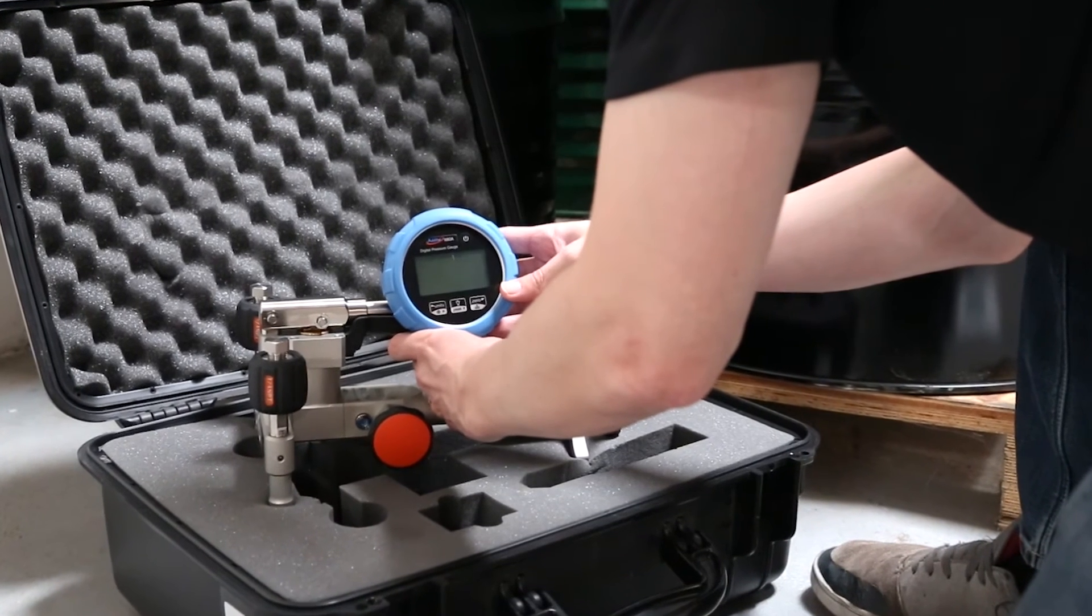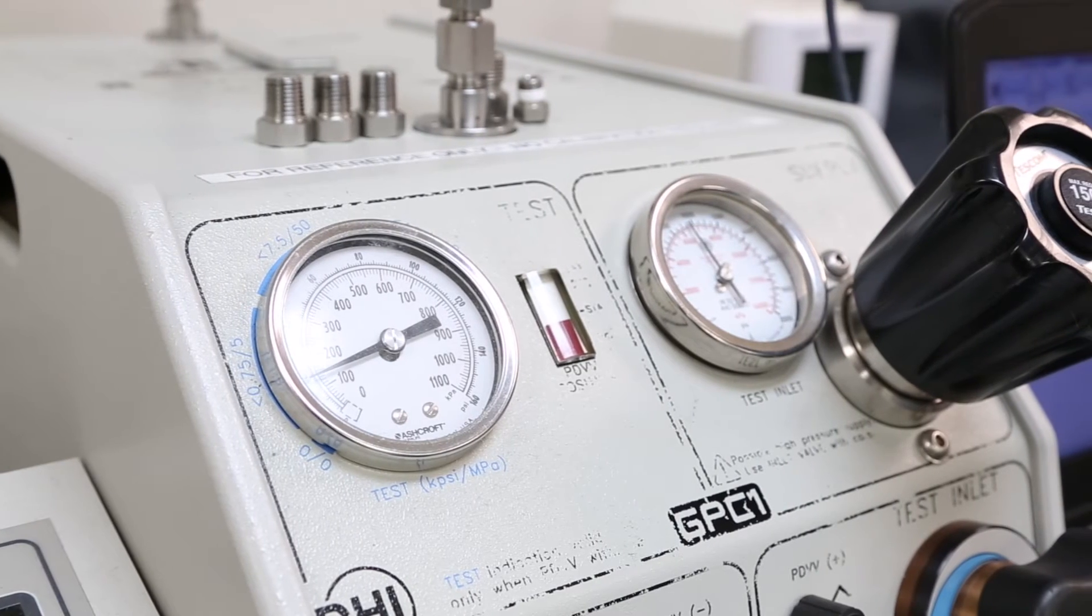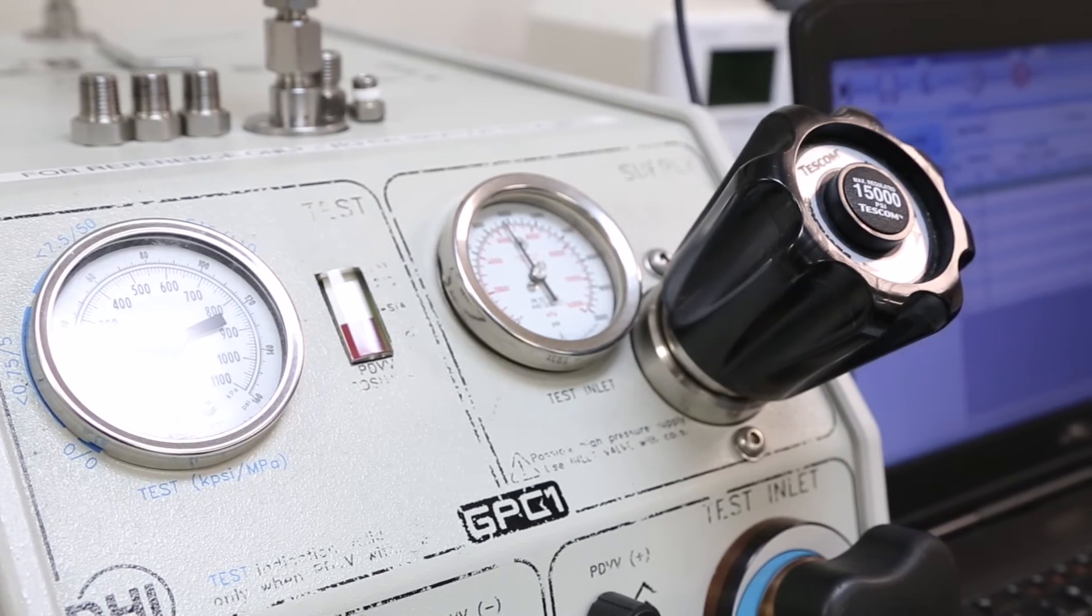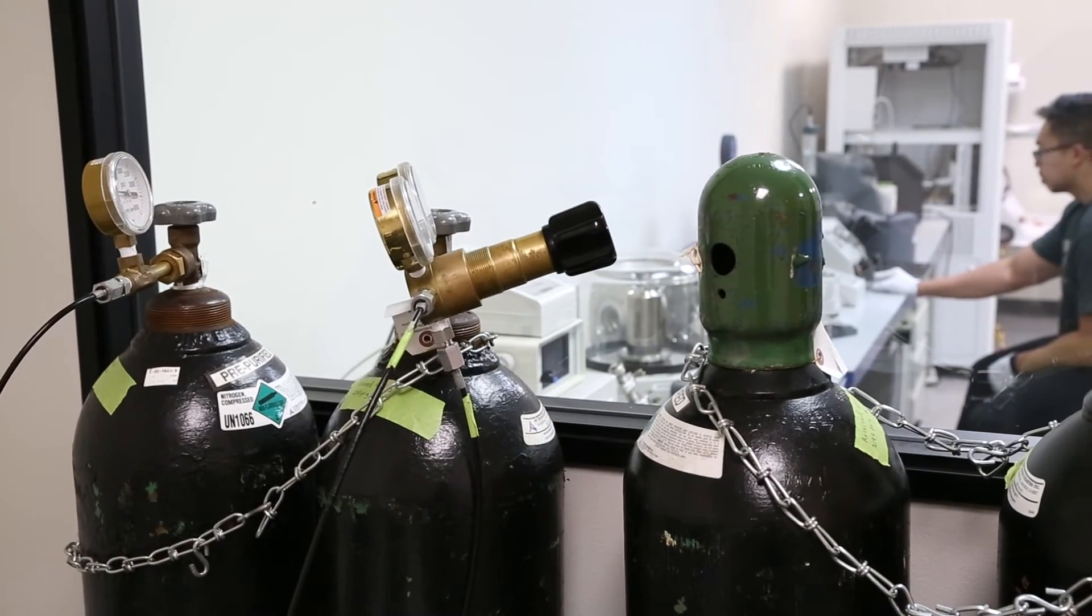To keep the piston in the deadweight tester afloat, pressure is needed to offset the amount of mass on top of the piston. To do this effectively, a pressure supply, most commonly either a gas bottle containing nitrogen or an electronic pump, is connected to a pressure controller.